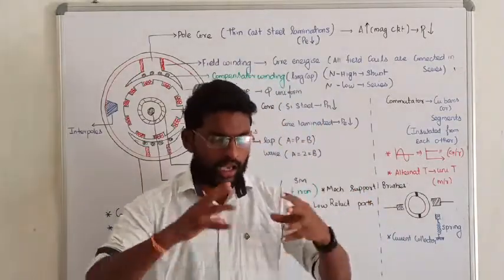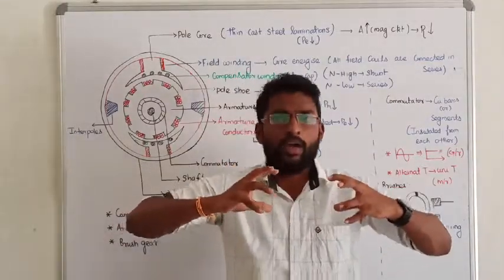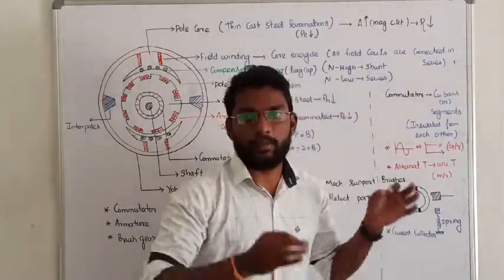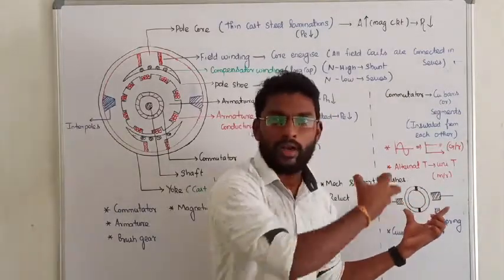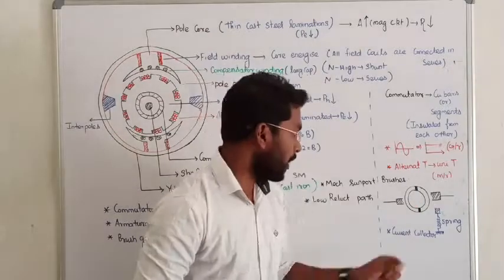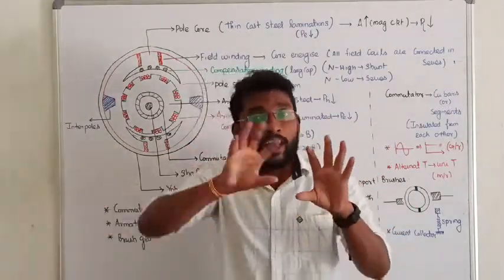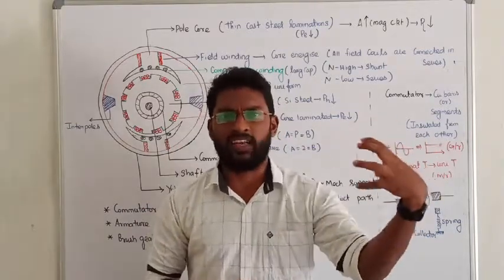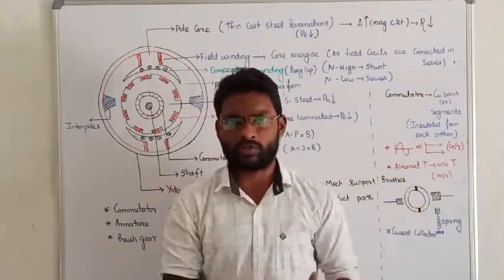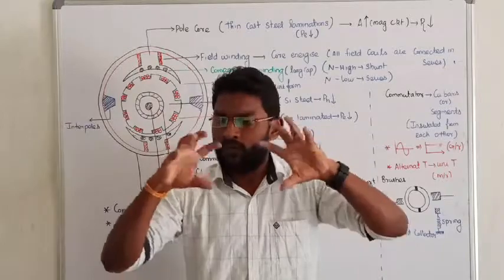The last component is the brushes. The brush is fixed and stationary, while the commutator rotates with the rotor. When the rotor rotates, the commutator rotates, but the brush remains fixed. The brush rests on the commutator and collects the current, then transfers it to the external load. That is the purpose of the brush. Usually, this brush is connected with a spring so that the spring maintains constant pressure between the brush and the commutator, ensuring good electrical contact at all times.